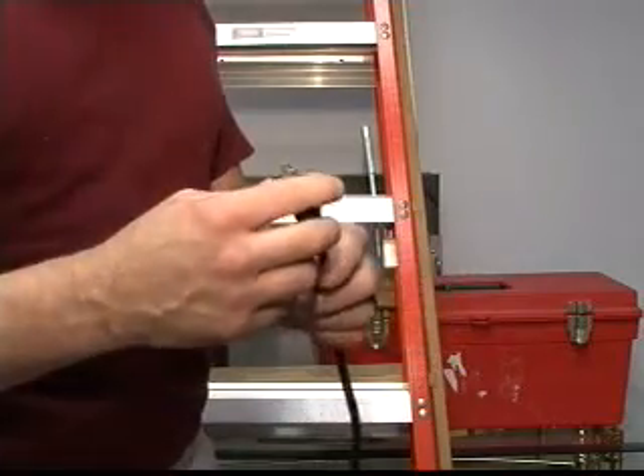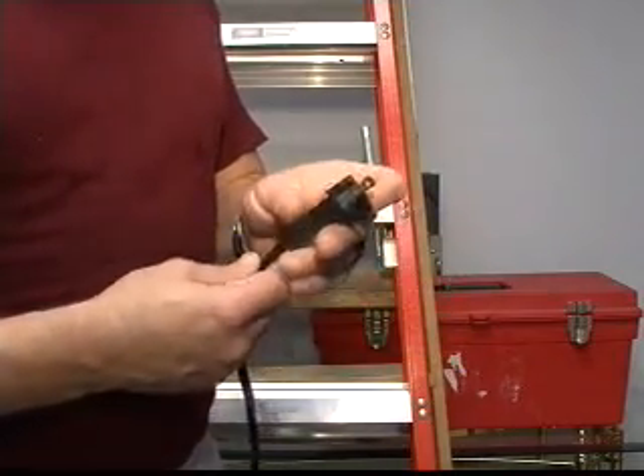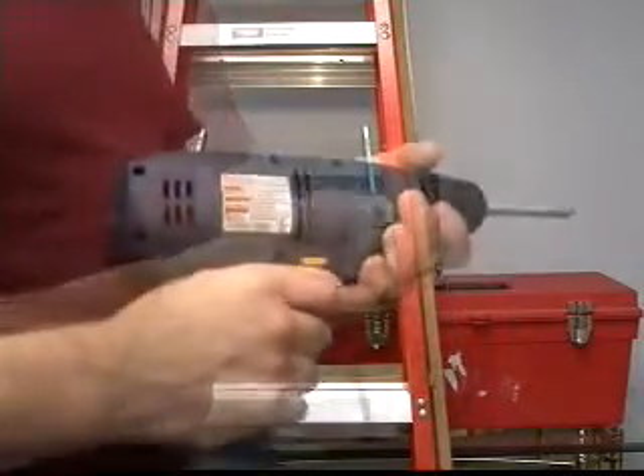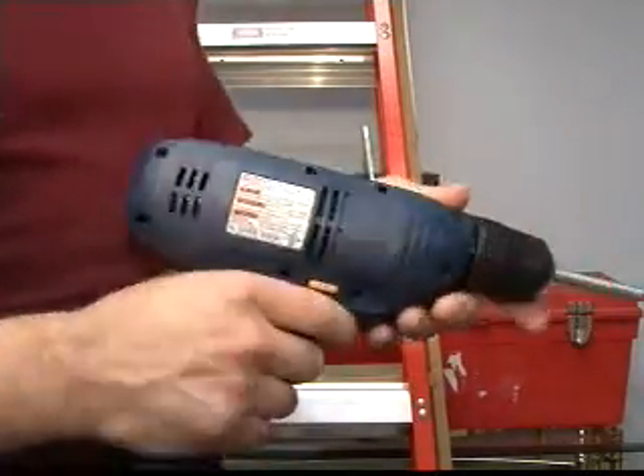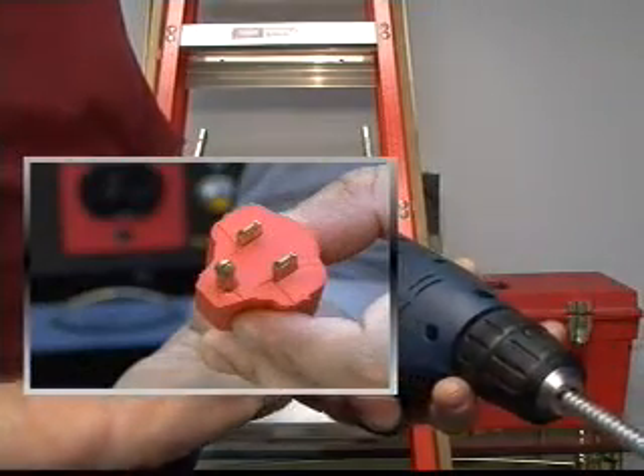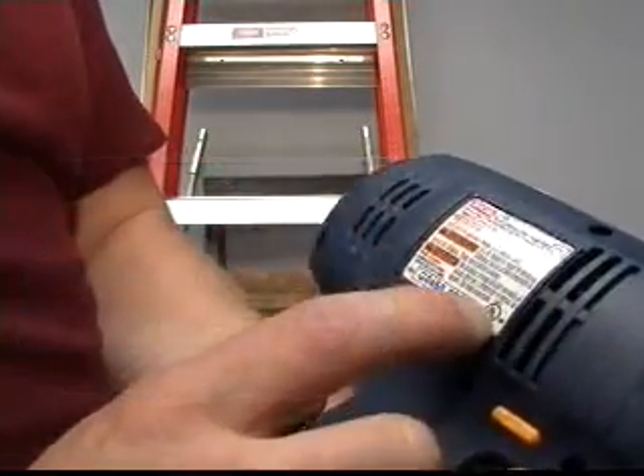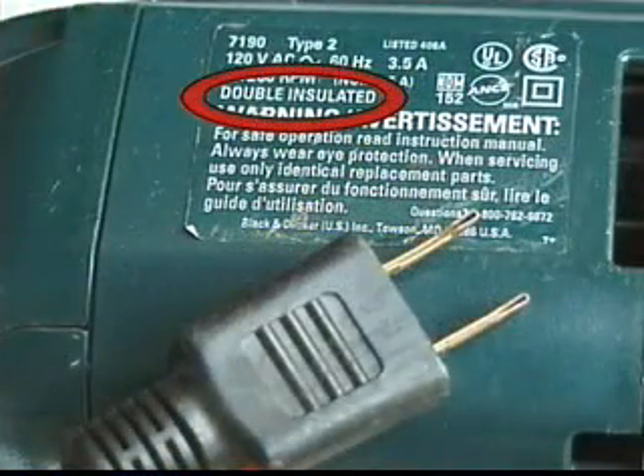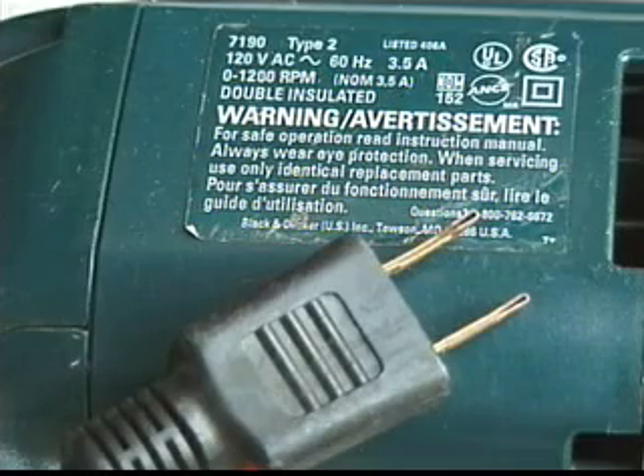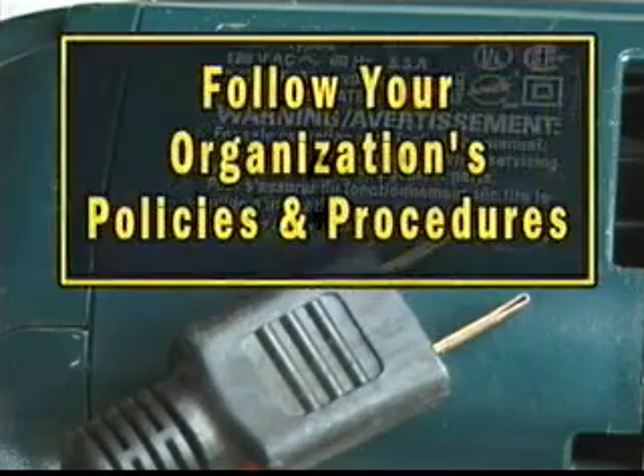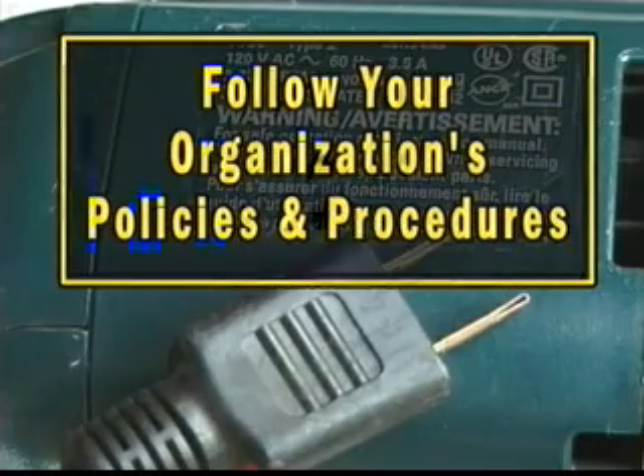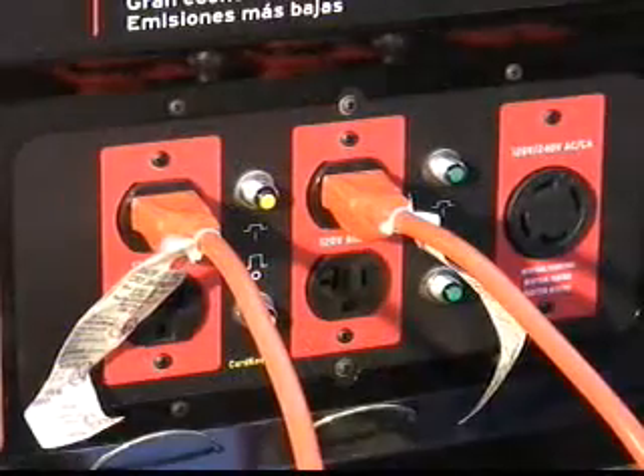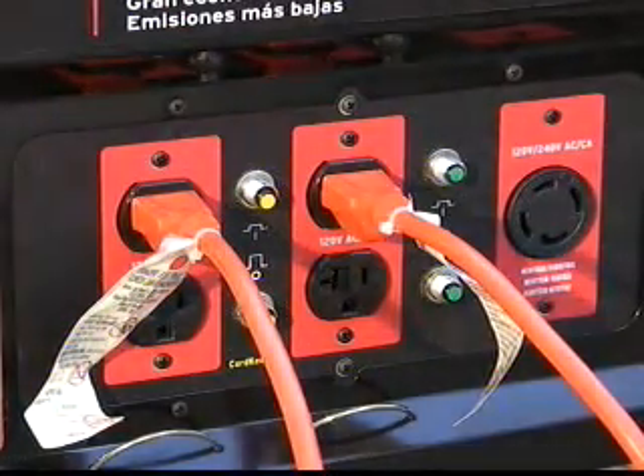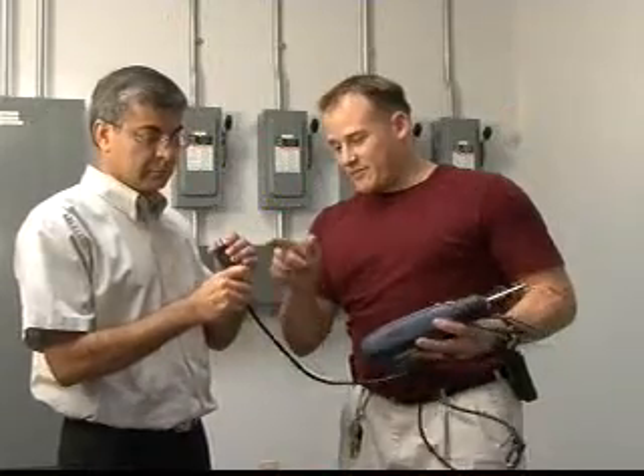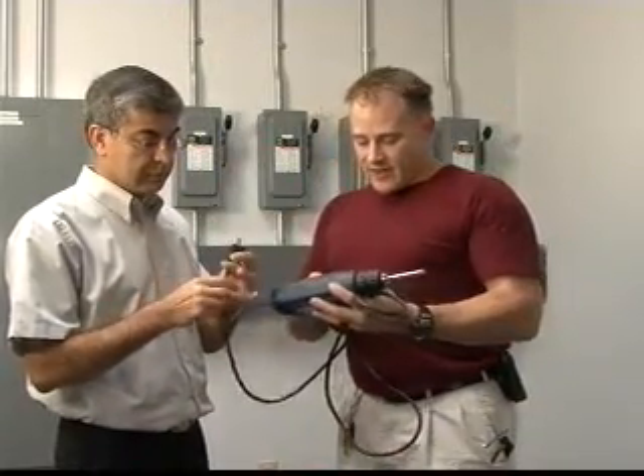There may be some approved appliances and tools in your work environment that use only the two-prong plug, as shown here. It can only be used with double insulated equipment. The protection is provided by double insulation inside the equipment and not through a grounding wire and grounding prong. The equipment must state double insulated on the manufacturer's data plate. If it doesn't state double insulated, then the third prong and grounding wire plugs must be used. Follow your organization's policies and procedures regarding this type of equipment, as each situation is different. It's up to your organization to make the determination of what type of electrical equipment to use.